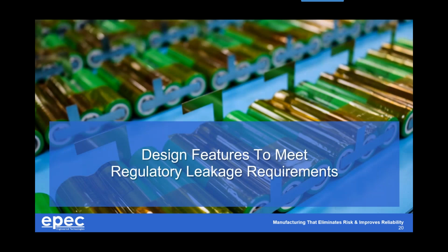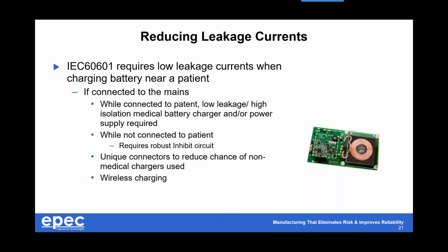So we'll look at some of the other features. Now, we talked mostly about the cell itself, the battery, some of the safety features. A couple other things at a system level: the 60601 standard requires low leakage currents if you're charging a battery near a patient. The reason is, when you're charging, that charger has to be plugged into an outlet or mains. So this becomes very important. If the patient is connected to the product and the battery is connected, it's absolutely mandatory that there's a very low leakage current in the microamps, and also a really high isolation voltage for nearby lightning strikes or what have you, so it doesn't jump the isolation gap. So you have to use a medical charger and/or power supply that's medically approved with the proper regulatory stamps and approvals. Very important, and it's absolutely mandatory, and 60601 calls it out.